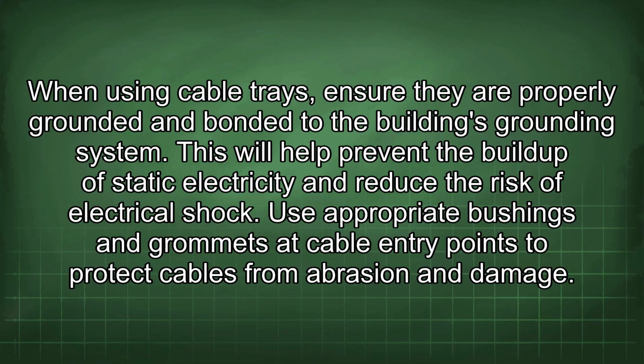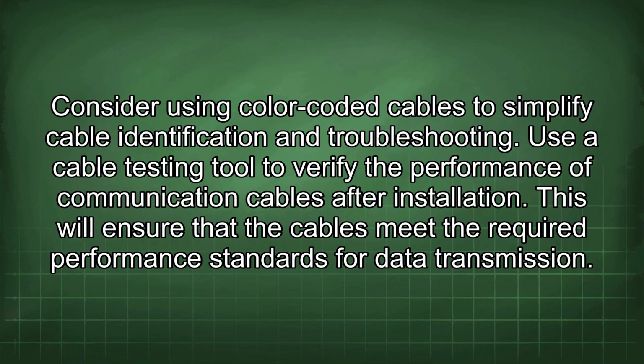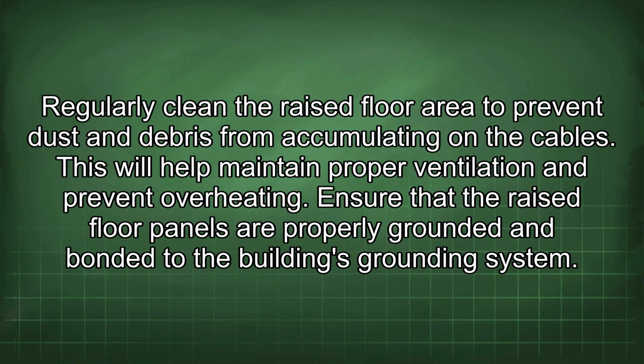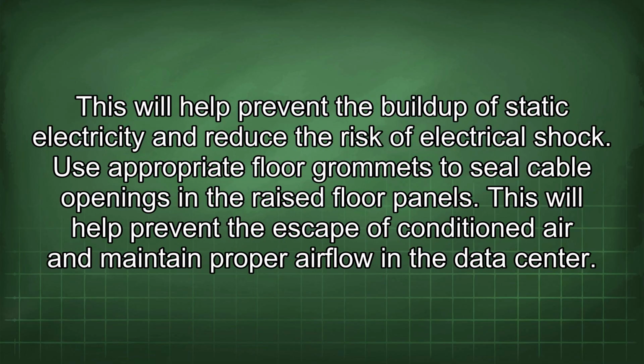Use appropriate bushings and grommets at cable entry points to protect cables from abrasion and damage. Consider using color-coded cables to simplify cable identification and troubleshooting. Use a cable testing tool to verify the performance of communication cables after installation. This will ensure that the cables meet the required performance standards for data transmission. Regularly clean the raised floor area to prevent dust and debris from accumulating on the cables. This will help maintain proper ventilation and prevent overheating. Ensure that the raised floor panels are properly grounded and bonded to the building's grounding system. This will help prevent the buildup of static electricity and reduce the risk of electrical shock. Use appropriate floor grommets to seal cable openings in the raised floor panels.